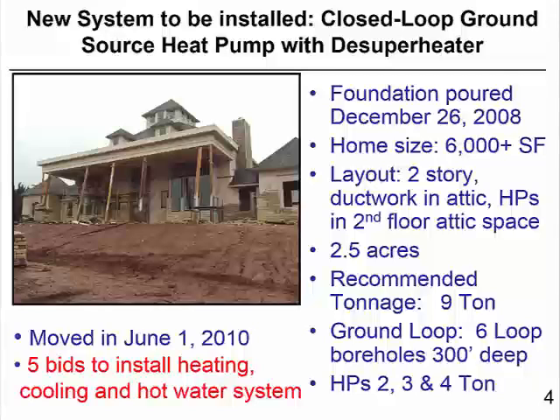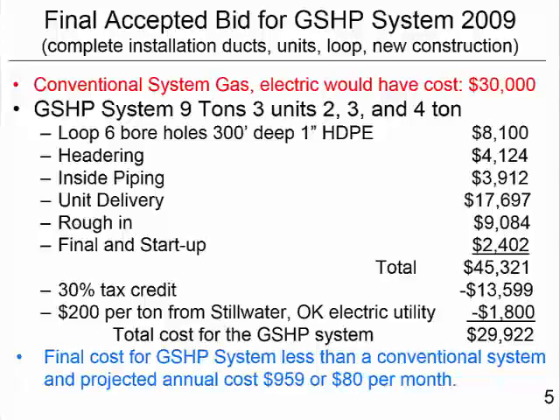I had 5 bids to install heating, cooling, and hot water systems. I was looking for conventional systems as well as ground source heat pump systems in the bids. The final accepted bid for the ground source heat pump system was in 2009, and it was for the complete installation of ducts, units, and loop field, all new construction for a newly constructed building. So it's for everything. A conventional system, a gas system, or electric, would have cost $30,000 for this. The ground source heat pump system, 9 tons, 3 units, 2, 3, and 4 ton. The loop field, 6 boreholes 300 feet deep with 1-inch HDPE pipe, was $8,100.